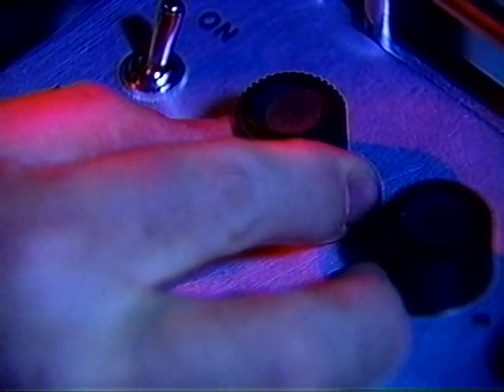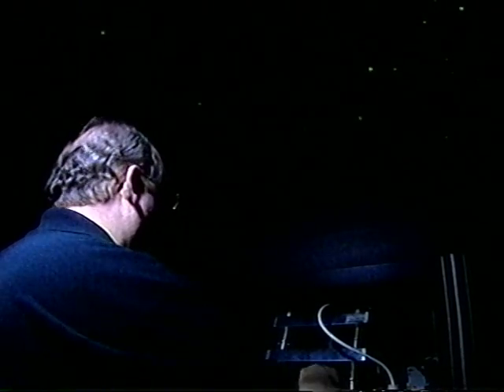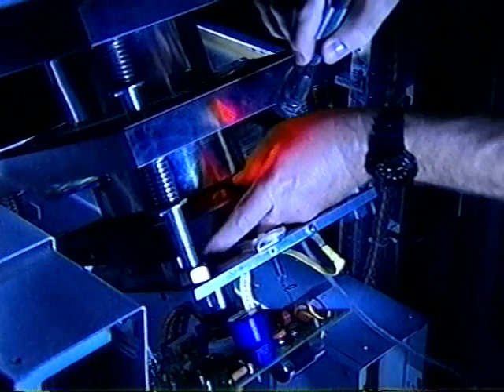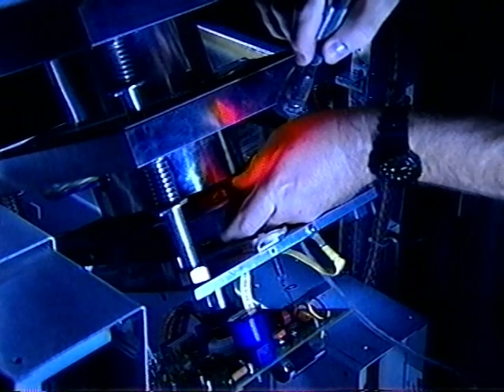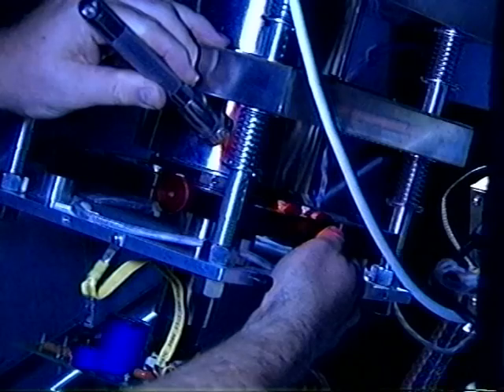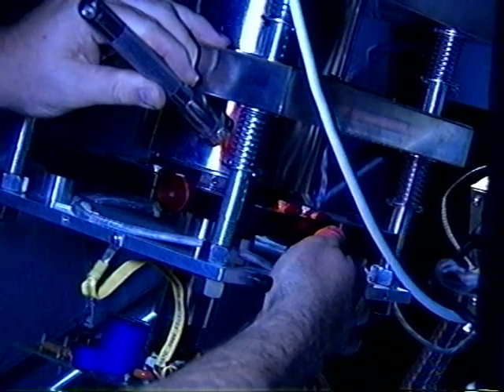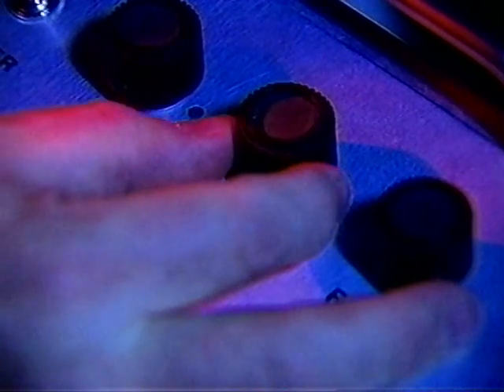The image will probably change position as it fluctuates in and out of focus. This indicates that the coil is out of alignment. The objective is to rotate the red wheels on the micropositioner until the movement is minimized. Begin by turning either the X or Y translate wheel. Rotate the wheel until the image movement is minimized or until it changes the direction it is moving. Now turn the other translate wheel and do the same. Do not look only at a single star during the alignment. Judge the entire picture. Repeat adjusting X and Y translate wheels until no further improvement is noticed.